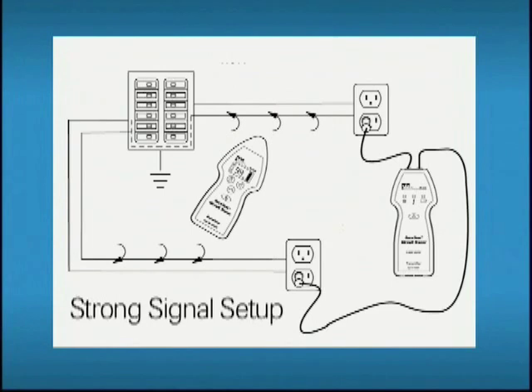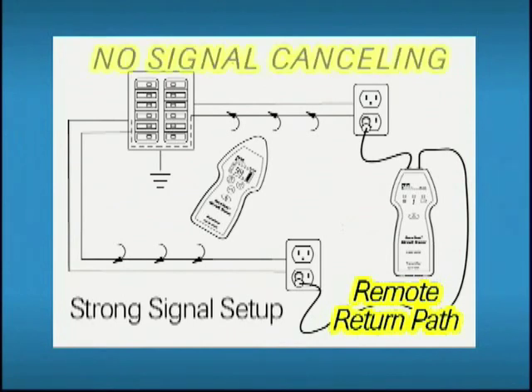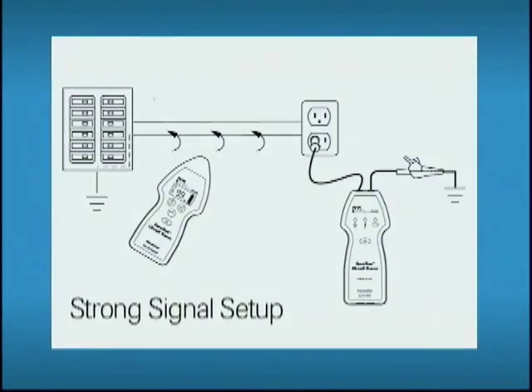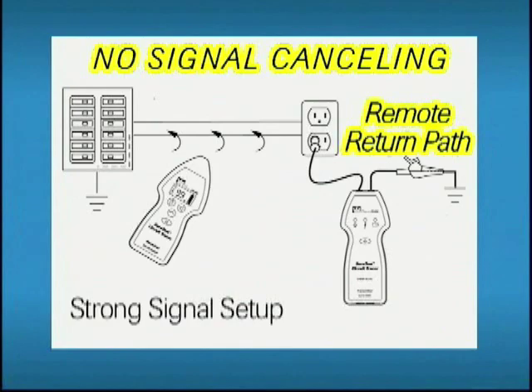To avoid this cancelling effect, one lead of the transmitter should be connected to the conductor to be traced, while the second lead should be connected to a remote return path. The simplest method is to use the 25-foot test lead to connect to a neutral or ground from another circuit, or connect to a ground source such as a water pipe or ground rod.